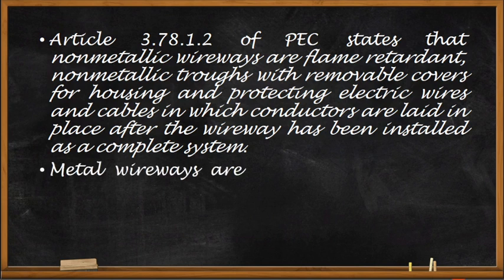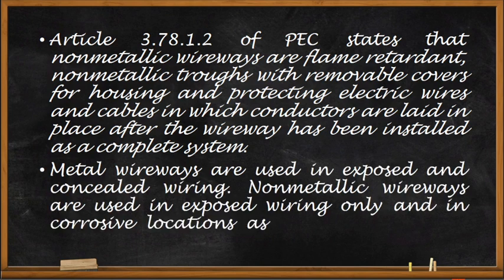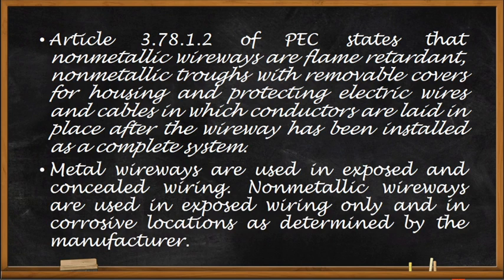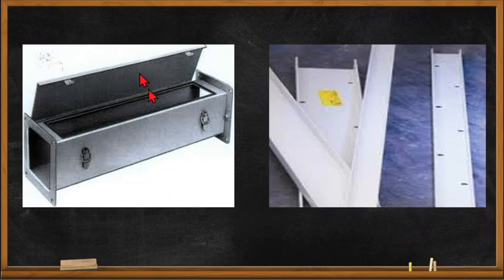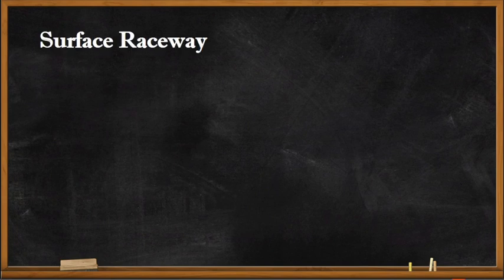Metal wireways are used in exposed and concealed wiring, while non-metallic wireways are used in exposed wiring only and in corrosive locations as determined by the manufacturer. Non-metallic wireways are preferred for corrosive locations because using metal wireways there would cause the metal to rust. This is an example of a metallic wireway and this is the non-metallic wireway.